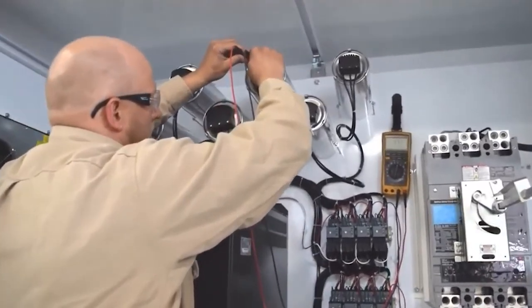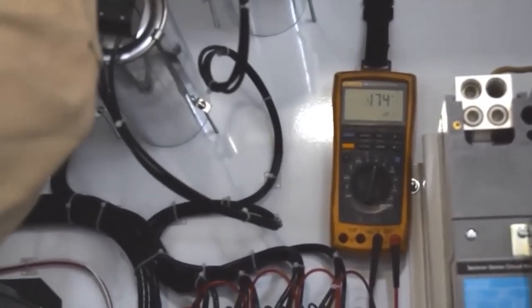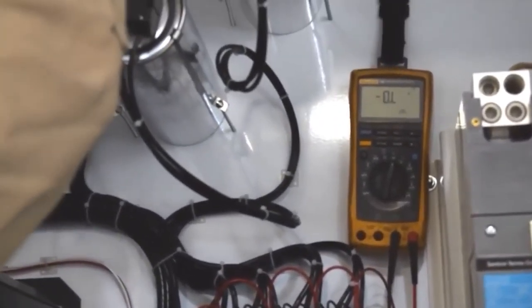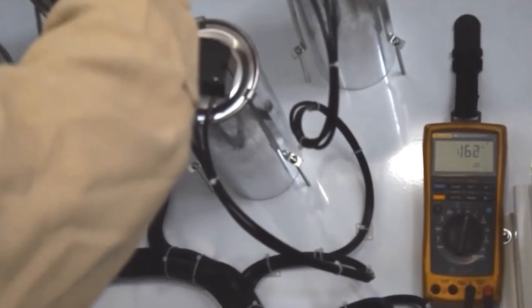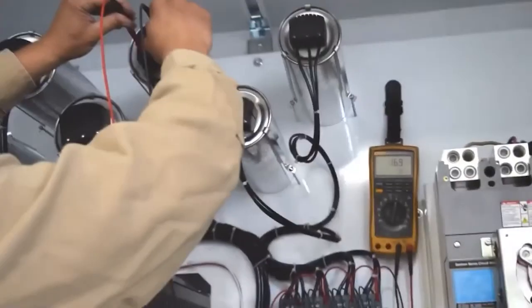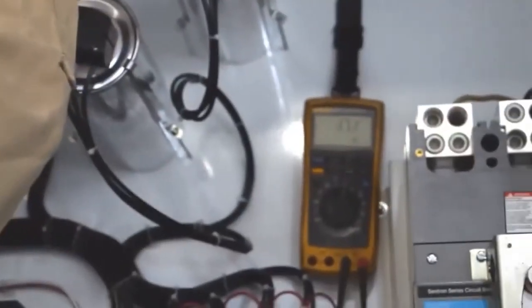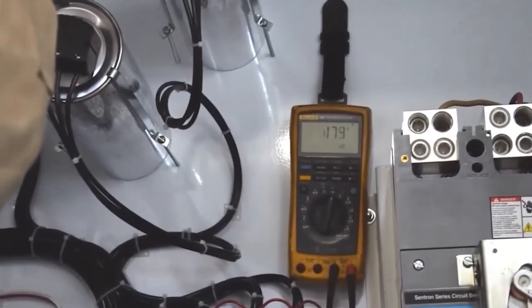So now I'm moving up to one of the bigger capacitors. Once again, we're going to do the same test, but my reading is going to be higher now because it's a larger kVAR capacitor. And on these ones, I'm getting about 175 microfarads from cap to cap.